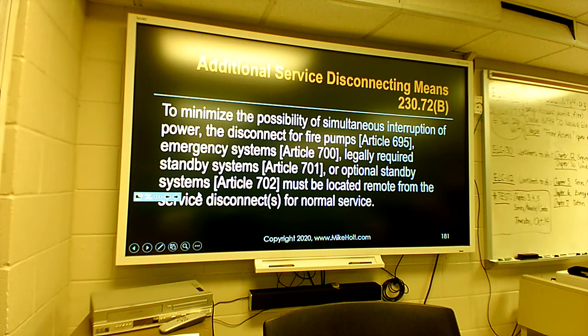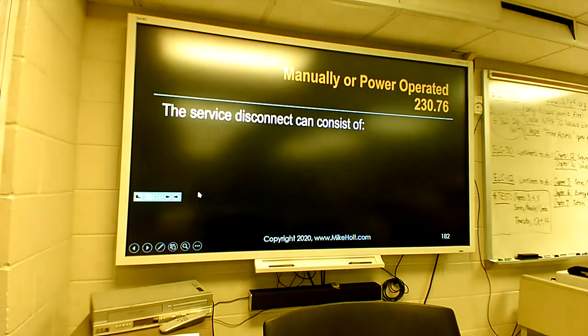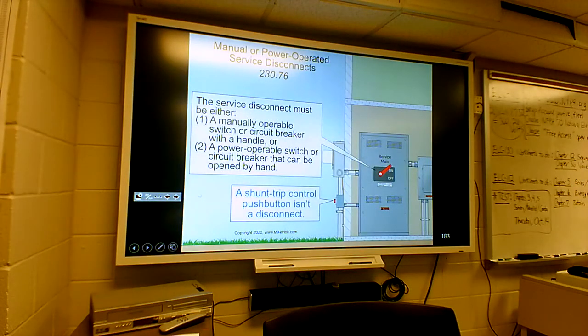To minimize the possibility of interrupting power for things like fire pumps, emergency systems, legally required standby systems, or optional standby systems, then you can have additional service disconnects. Manually or power operated, the disconnect can consist of a manually operated switch or a power operated switch that can be opened by hand.